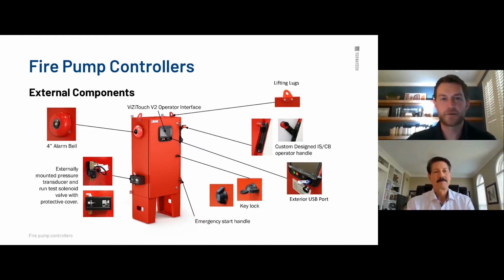All right, I'll jump in with the external components on the control panels. I think we've mentioned the bell a few times. I don't know if it's 85 or 95 decibels. It's pretty loud. You can hear it very clearly, especially when you're standing right next to it. Our externally mounted wetted parts here, that's the pressure block, the pressure transducer. The ViZiTouch here, that's our brain of the panel, the computer basically. Our flange mounted operator. The emergency handle is down here. We mentioned that one earlier as well.